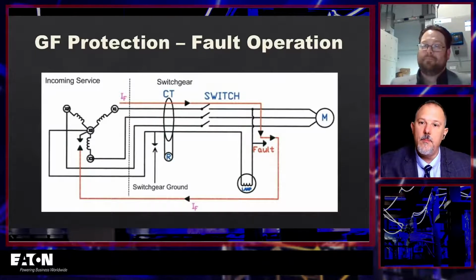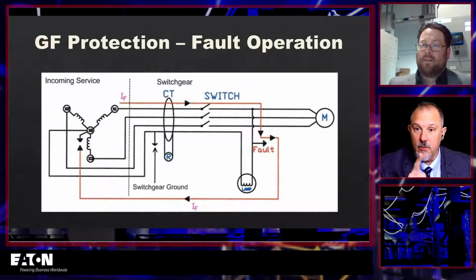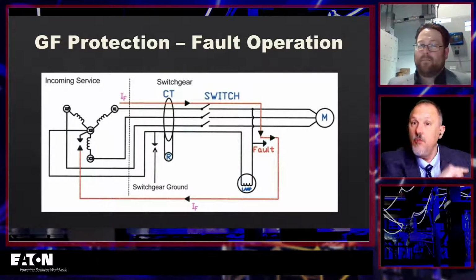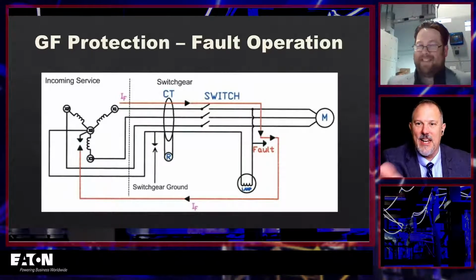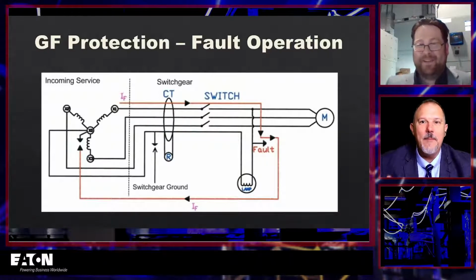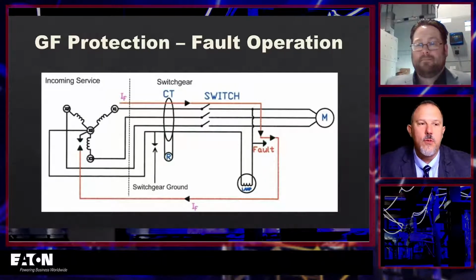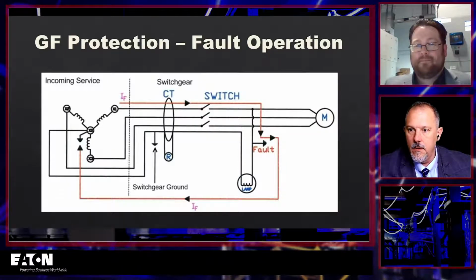He says it's all about the fact that you're going to have a low fault current, and you won't trip the overcurrent protective device. And I said, well, that's why I will have ground fault protection of equipment, because of what you just said. When I have a fault current that is lower, I'm not required anywhere in the code to have a fault current greater than the long time pickup or short time pickup or the instantaneous. All I have to do is protect the conductor, which we do with overcurrent protection. And we know overloads can exist. I'm not going to damage the insulation.